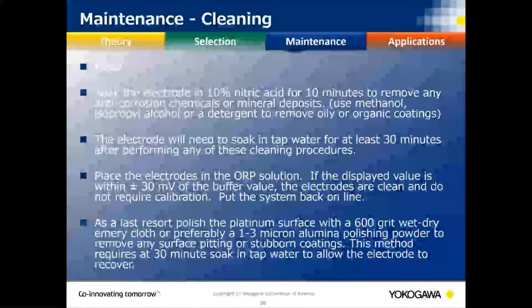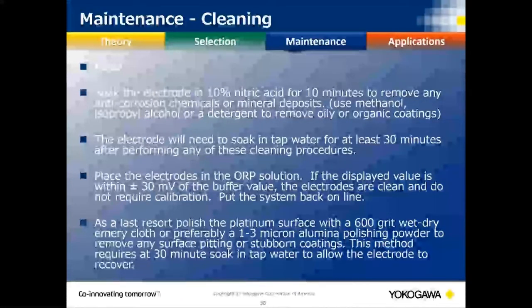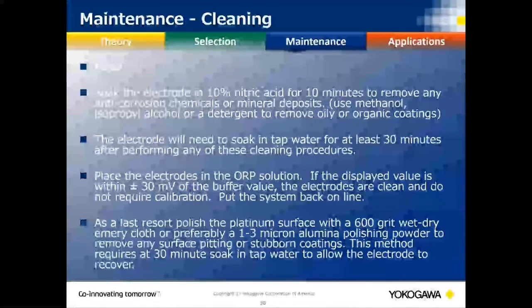Just as with pH — if you're within 0.03 pH you don't need to recalibrate — with ORP, it's honestly only accurate within plus or minus 30 millivolts. If you're within that range, you can put it back without calibrating, unless your SOP requires it.